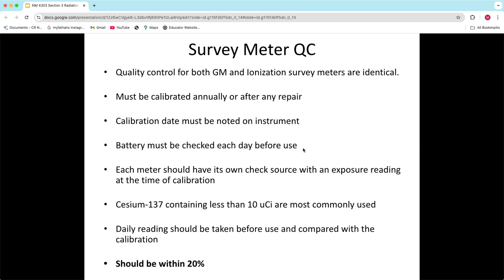Now, what a lot of you probably do at your sites is you get the reading and then you go to a computer and you have something that keeps track of all your hot lab QC stuff, and you put a number in, like maybe your reading is 0.02 or 0.05, whatever it is, and you put that in. And what's happening in that software is, whatever tech is in charge of your meters, when those meters were received, he took the reading on the sticker that said what it should be, and he just put that in your computer software, right? And so that's how it's checking.